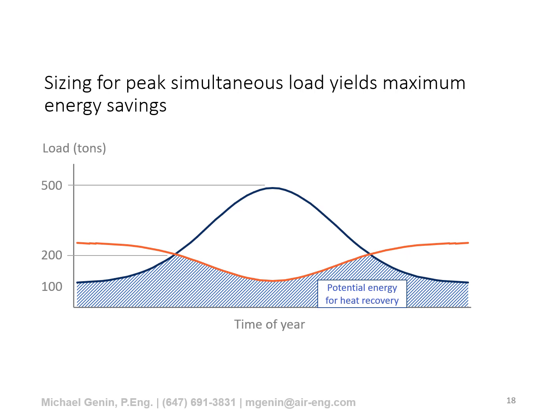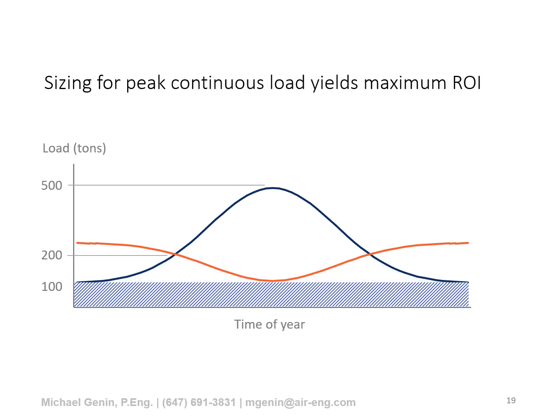So what ends up happening here is the area I've shaded in blue is a potential energy for heat recovery. This can be achieved completely with the heat recovery chiller or heat recovery unit, and there's no need to burn any new fuel in order to meet this heating demand. So sizing the heat recovery chiller for a 200-ton peak, which is the equilibrium in this case, might have the greatest impact, the greatest carbon emissions reduction. The most cost-efficient way to do this would be to size the chiller for a 100-ton load. That would be represented by this blue shaded area.